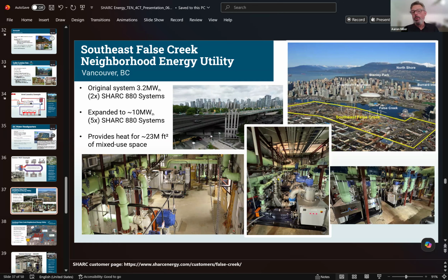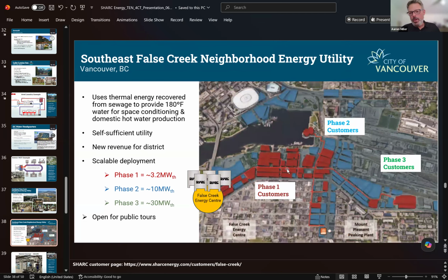We're now harvesting almost 10 megawatts of thermal energy, powering 23 million square feet of mixed indoor space in Vancouver. And it's so successful, they're already trying to figure out where they can fit a couple more units because they want to biggie size it. So, round one, phase one with these red buildings, and this is 100% sewer, nothing else. Phase two, we're now powering the blue areas. They want to now pick up these additional industrial areas in the dark gray.